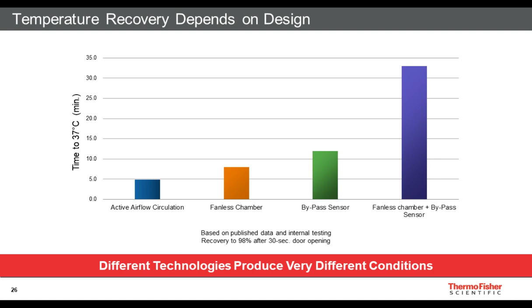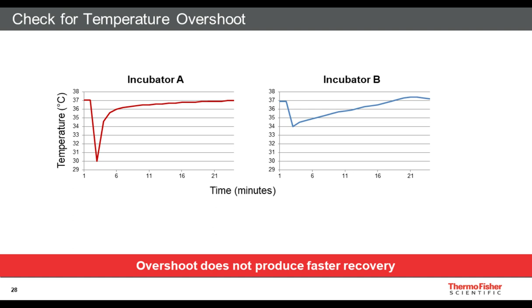The other thing that you might see in a brochure, for example, is that in trying to hurry or speed the recovery of temperature after a door opening, you can see an overshoot of the desired temperature. So here's a recovery graph from one incubator on the left that shows a speedy recovery to about 36 degrees, and then it slows as it approaches 37 degrees. And then if you focus on the graph for incubator B, you can see it's actually a slower recovery, and then when it hits 37 degrees, it keeps going, so it overshoots 37 degrees. And as we've just established, higher temperatures are actually more detrimental for cells. So overshooting that set point of 37 degrees does not produce faster recovery, and it can be detrimental to cells.